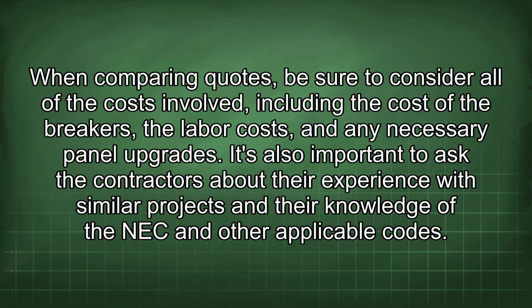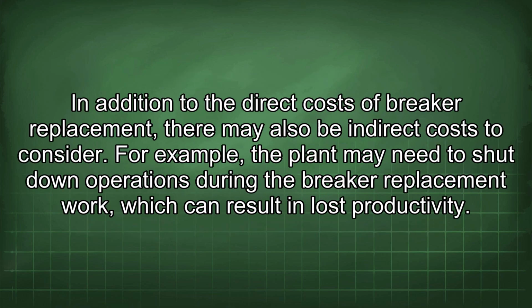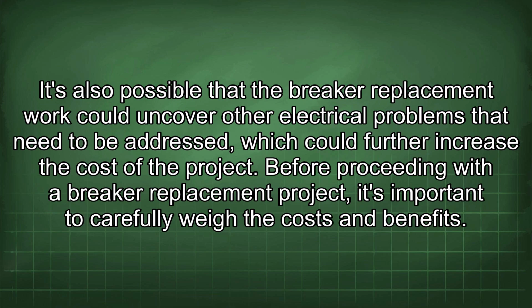When comparing quotes, be sure to consider all of the costs involved, including the cost of the breakers, the labor costs, and any necessary panel upgrades. It's also important to ask the contractors about their experience with similar projects and their knowledge of the NEC and other applicable codes. In addition to the direct costs of breaker replacement, there may also be indirect costs to consider. For example, the plant may need to shut down operations during the breaker replacement work, which can result in lost productivity. It's also possible that the breaker replacement work could uncover other electrical problems that need to be addressed, which could further increase the cost of the project.